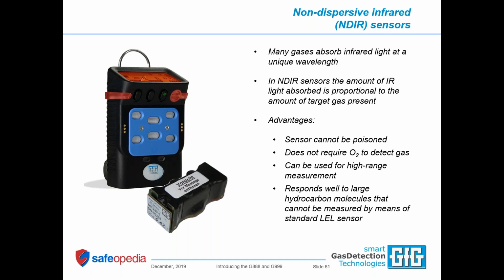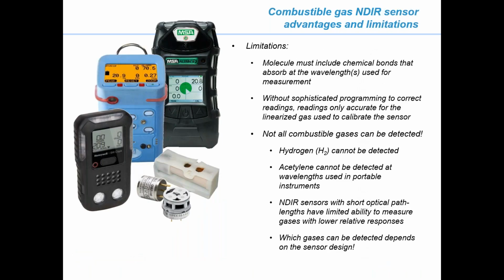The IR LEL sensors don't require the presence of oxygen to detect gas. They can't be poisoned. You can use them for high-range measurement without damaging the sensor. And again, they respond very well to vapors that can't be detected with the catalytic LEL sensor. Now, when it comes to limitations, you need to consult the owner's manual because the limitations of one manufacturer are not necessarily the same limitations for another manufacturer. So the limitations are, first of all, the molecule has to include chemical bonds that absorb at the wavelengths that you're using to measure the gas.